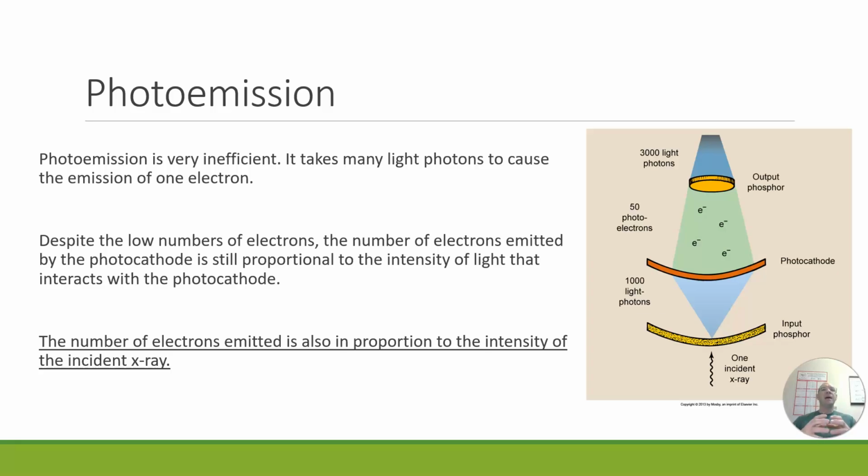make up a pattern that matches what the X-ray image is. Okay, so all of the electrons that are popping off, where there's strong X-ray, there's a lot of electrons. Where there's dim X-ray or dim light, there's less electrons. Where there's no X-ray, there's no electrons. But those electrons are held in place. Those electrons cannot move. And so if you could just think of an X-ray image, if you could take a bunch of electrons and look at it as an image, it matches the X-ray image that you're eventually going to see.